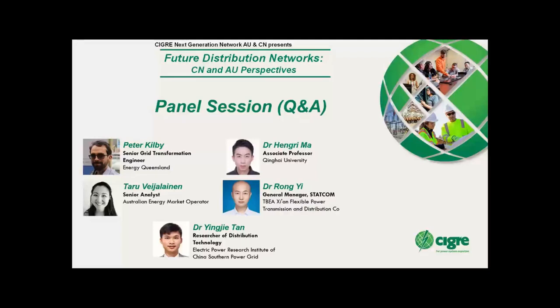But as Peter and Taru mentioned in the presentations, you have proposed some solutions to address the issues caused by distributed photovoltaic in the distribution network. For example, the solution you are proposing, the new voltage standard from 240 to 230, can leave some space for more penetration of photovoltaic. But this is from the voltage point of view, and the active power is still a problem, I think. For example, the reverse power flow to the distribution transformers. So from my point of view, this is not the ultimate solution for the problem caused by the high penetration of distributed PV.